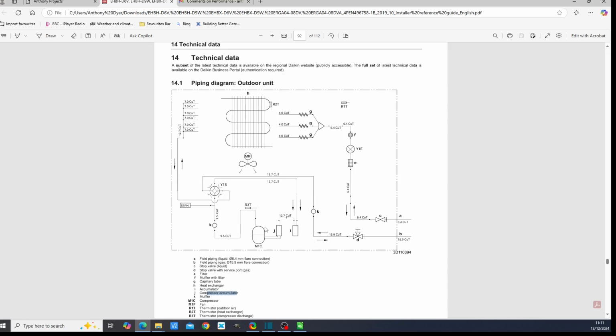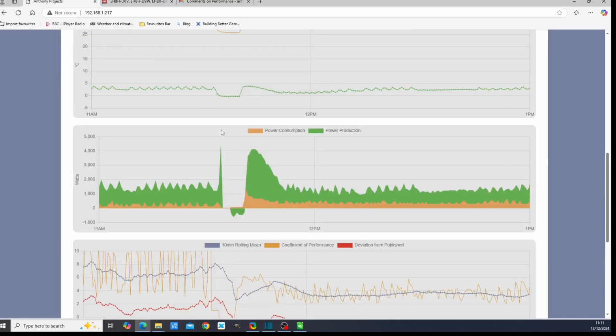And so long as this regime exists, where your compressor kicks in every 2 minutes, as we've seen, you can actually achieve a full phase change through here at a much reduced flow rate, simply because your compressor is only running for 25% of the time at the minimum rate. That's how you can do it.